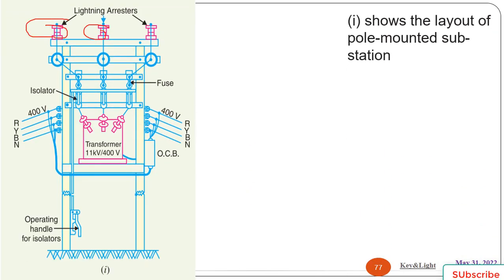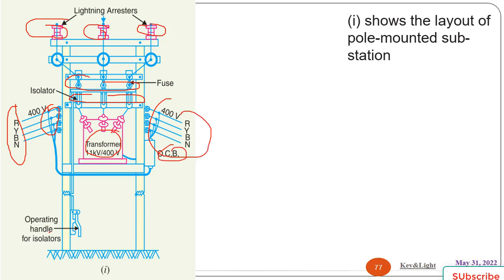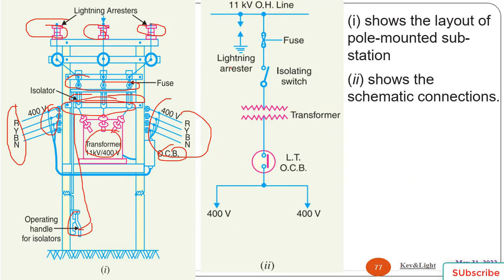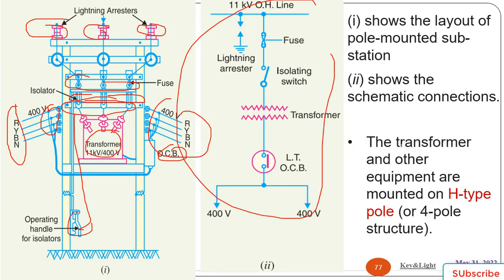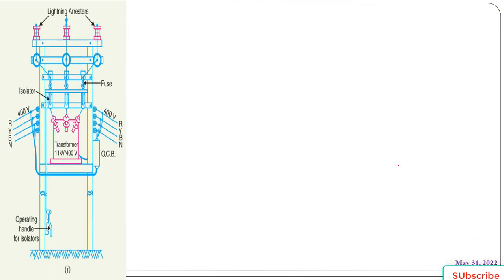The other is, these are lightning arresters. This is a transformer, and these are fuses, these are isolators, and this is the output of the transformer, which steps down 11 kV to 400 V, and this is the oil circuit breaker operating handle to disconnect the isolators. And this shows the schematic single line diagram. The transformer and other equipment are mounted on an H-pole. This is the H-pole.